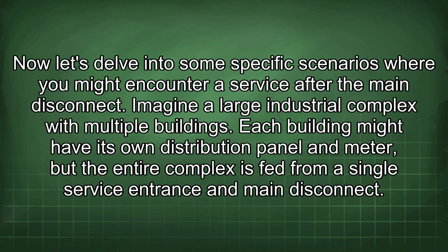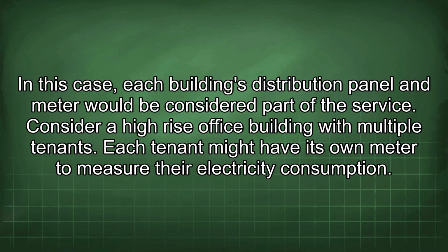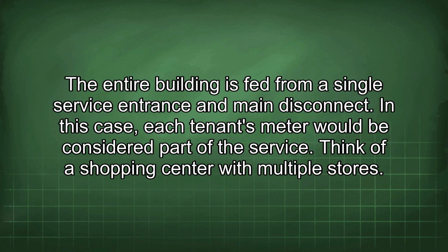Imagine a large industrial complex with multiple buildings. Each building might have its own distribution panel and meter, but the entire complex is fed from a single service entrance and main disconnect. In this case, each building's distribution panel and meter would be considered part of the service. Consider a high-rise office building with multiple tenants. Each tenant might have its own meter to measure their electricity consumption. The entire building is fed from a single service entrance and main disconnect. In this case, each tenant's meter would be considered part of the service.